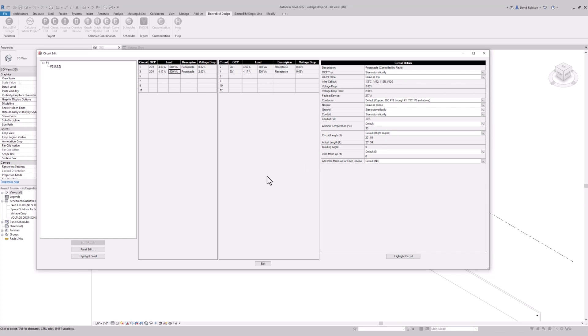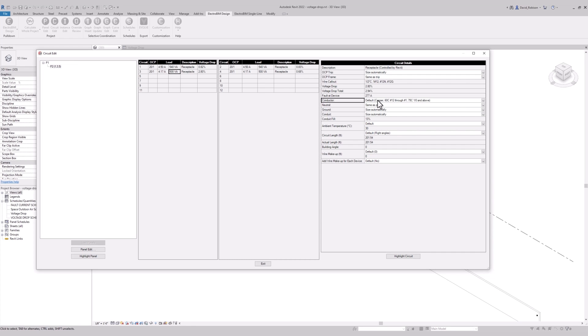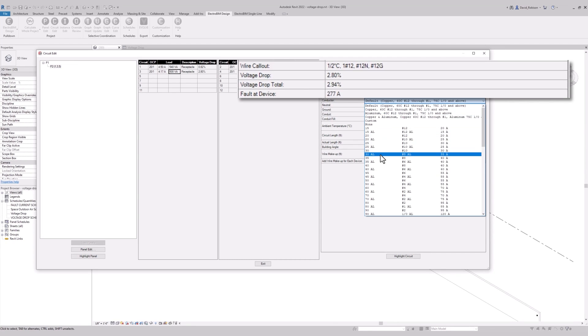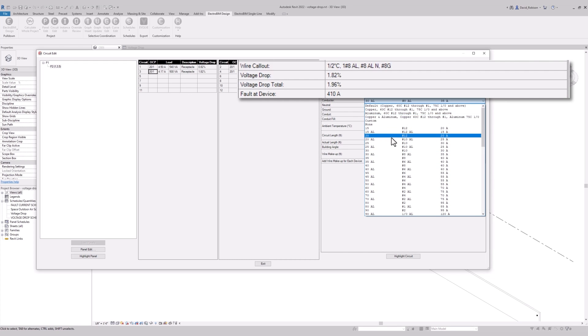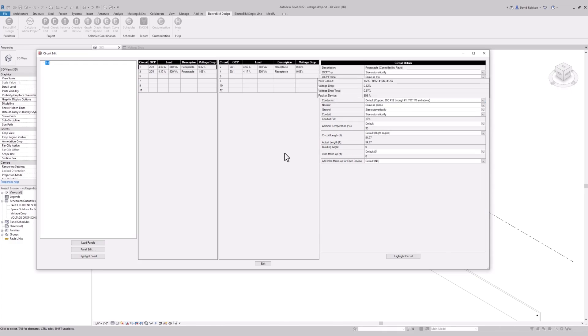Finally, for the wire size, we give you good defaults but we let you change those. Out of the box it's going to be sizing to copper, but if you want to, you can size the wire to aluminum, and when we do that the voltage drop is going to update. You can also change the wire size — if you want to use a different size copper wire, you can do that and the voltage drop is going to update. We've even got options for equipment versus service grounds based upon the type of device you're connected to. So we try to have lots of good defaults for wire sizing, but we let you as the engineer override those values as appropriate.